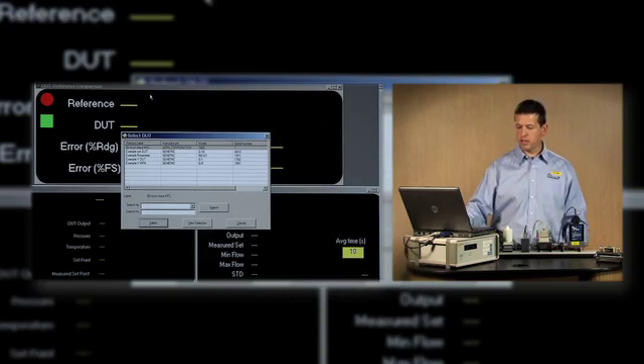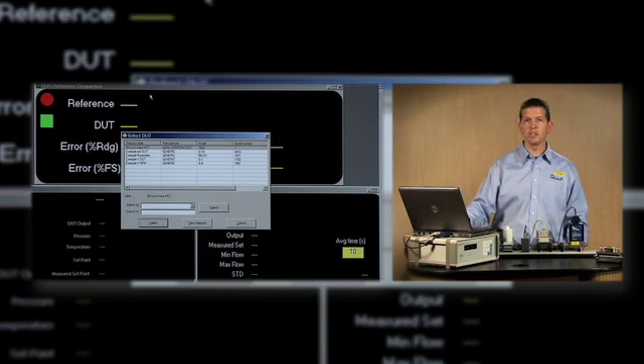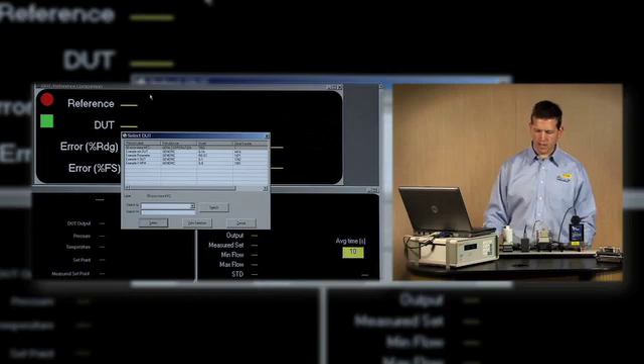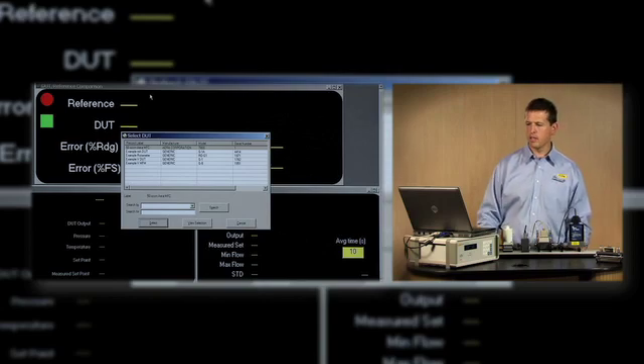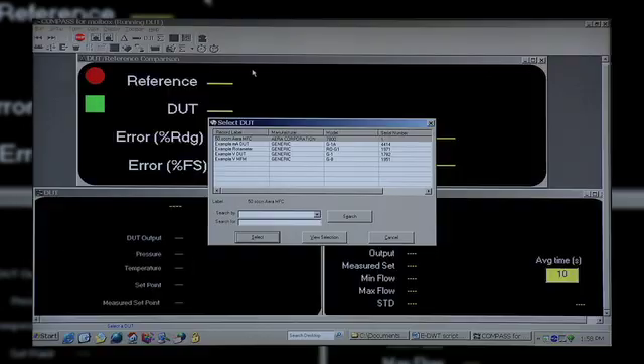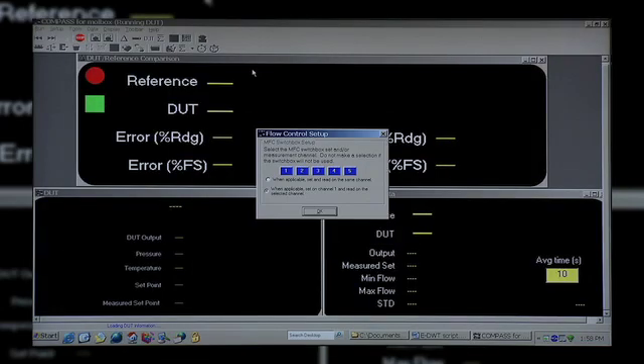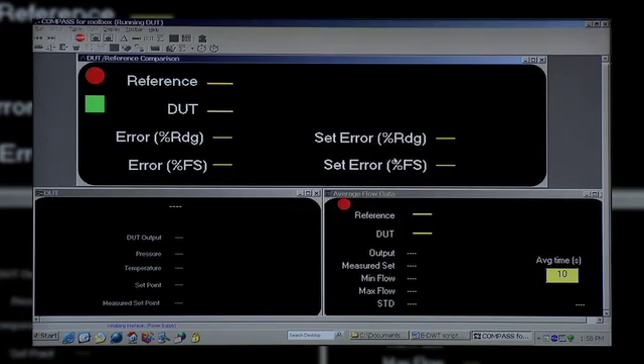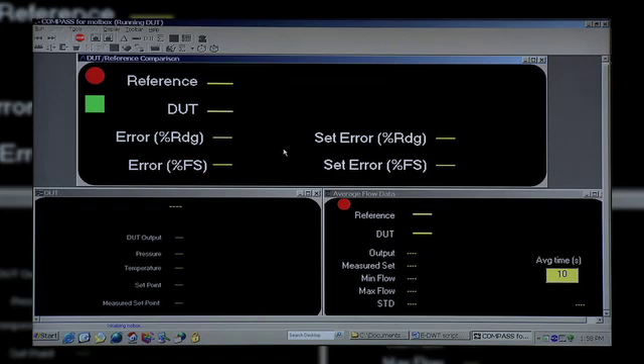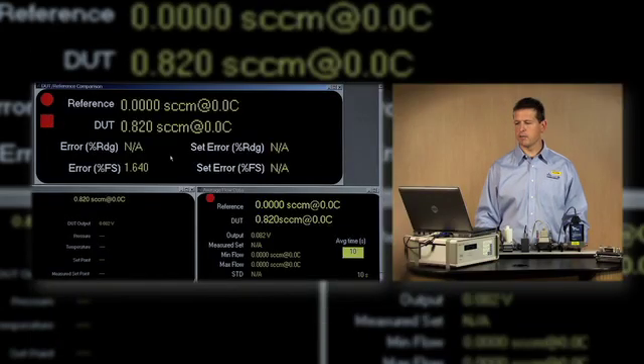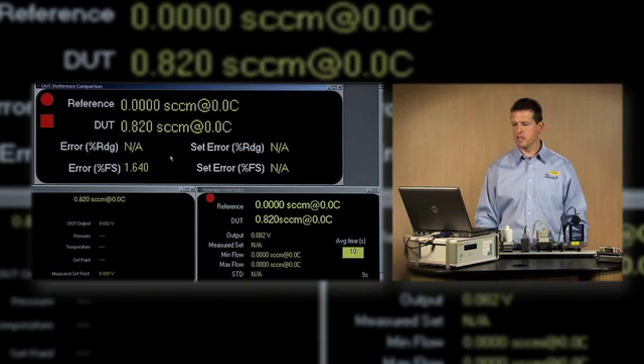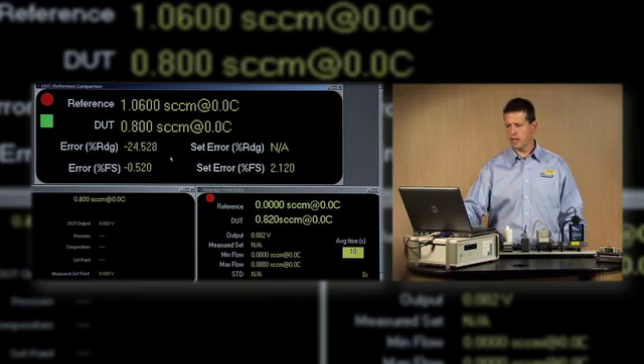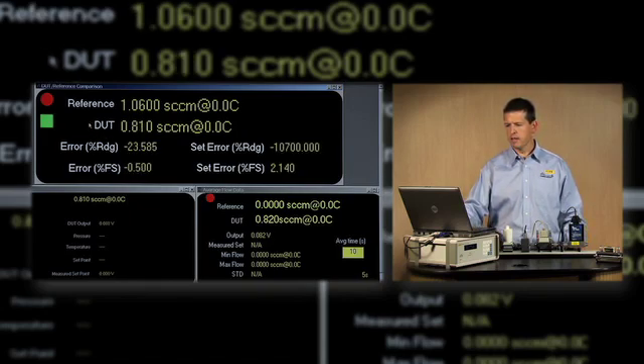This could be done just as easily using the front panel of the Molbox and just taking those readings live instead. I'll select the MFC as my device under test. A few default options and now Compass is initializing. We almost immediately get readings out of Compass and we see a reference indication and a device indication up at the top.